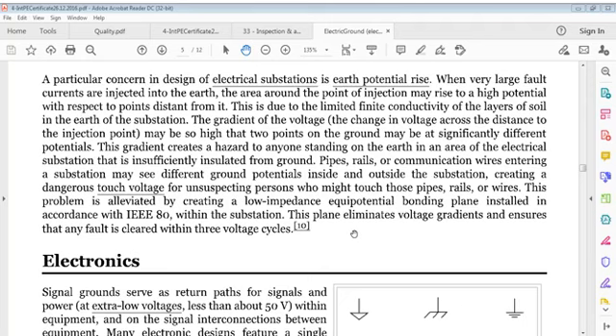Gradient of voltage, the change in voltage across distance to the injection point, may be so high that two points on the ground may be at significantly different potentials. This gradient creates a hazard to anyone standing on earth in an area of an electrical substation that is insufficiently insulated from ground.